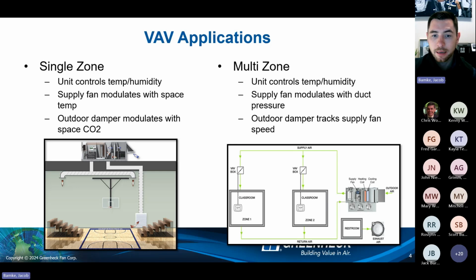So typically a temperature sensor tied to those VAV boxes is going to open and close them based on those classroom requirements and the amount of air that we need to cool down that space. But as those VAV boxes close, that means that those space set points are met, which means that we can reduce the supply fan speed. So you get really good part load fan savings from a multi-zone VAV application.